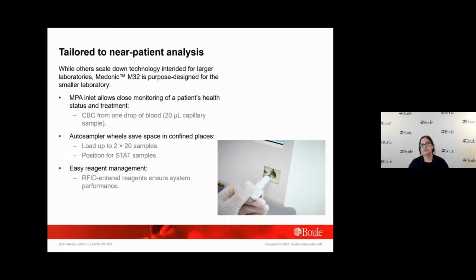One competitive advantage with Medonic M32 is that the system is tailored to the smaller laboratory by design. Instead of incorporating technologies and methods initially intended for the larger laboratory, Medonic M32 is purpose-built for decentralized testing, with a capillary sample inlet that allows close monitoring of patients and the space-saving automation wheels. RFID-locked reagents not only secure the very important after-sales, but also the use of designated reagents to ensure analytical quality and performance of the system.